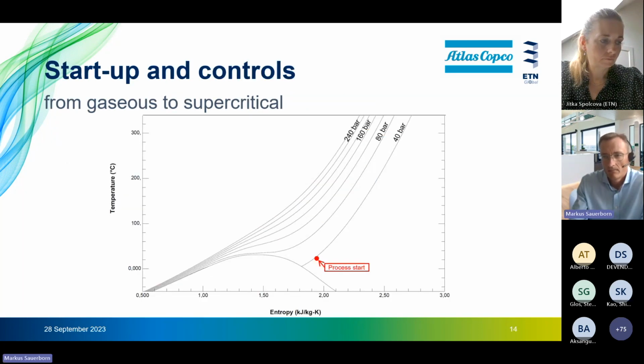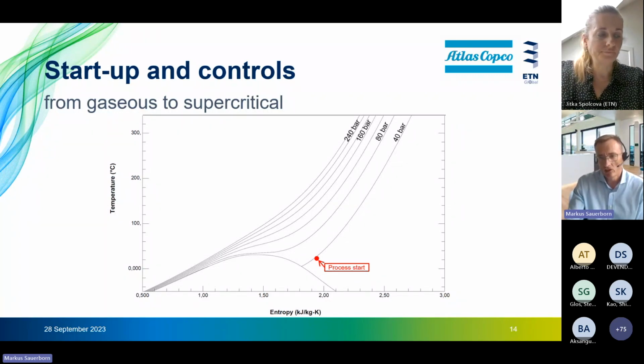So finally, startup and shutdown of the machine was a further challenge, as we have to bear in mind that the expander and the compressor are running on the same pinion in closed loop operation. This means in order to avoid overloading of the axial bearing, compressor and expander pressure have to be controlled over a relatively narrow band, especially during startup and shutdown procedure. The initial starting conditions of the loop were determined at around 38 bar, and the minimum starting temperature of 20 degrees C is required to avoid starting in the two-phase region.